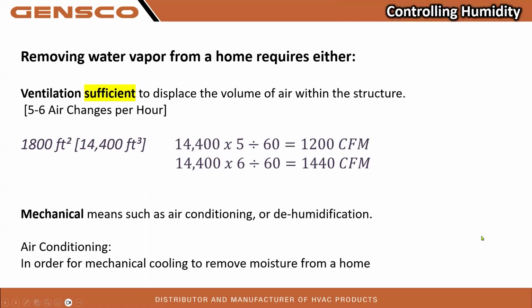Now, removing that water vapor from inside a home requires sufficient ventilation to displace the volume of air within the structure, and that has been pegged at 5 to 6 air changes per hour. So if we're talking an ERV, in an 1,800 square foot house, which with 8-foot ceilings is 14,400 cubic feet, we need 5 air changes divided by 60 minutes in an hour. That would be 1,200 CFM of ventilation to completely displace the air in the house 5 times. That's one way to deal with humidity, and that's pretty excessive.